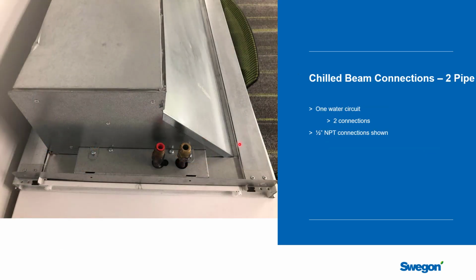Now this is a 2-pipe chilled beam, and you can see we're down to 1 set of connections. In this case, 1/2-inch MPT threaded fittings have been added to the coil. You can see all kinds of connections on chilled beams, and it'll just depend on the manufacturer and what the engineer wants to specify.